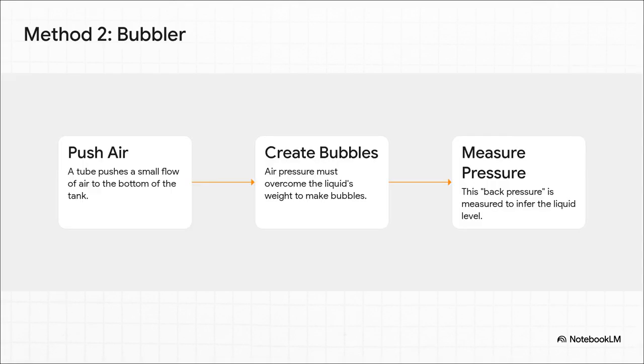Method number 2 is super cool: it's called a bubbler system. You have a tube that goes all the way to the bottom of the tank, and it just lets out a constant, tiny stream of air bubbles. To make those bubbles, the air has to push against the weight of all the liquid above it. The amount of pressure it takes to do that, what they call the back pressure, tells you exactly how high the liquid is. It's genius really, because the sensor itself never even has to touch the fluid.